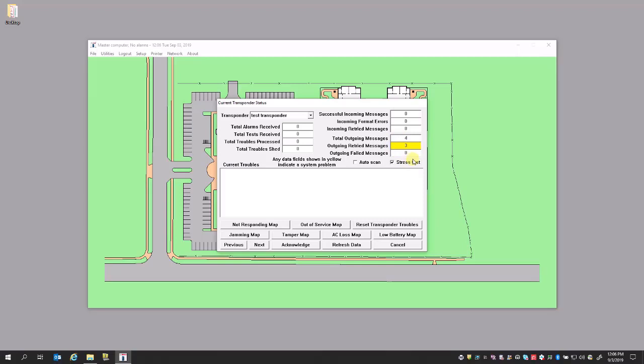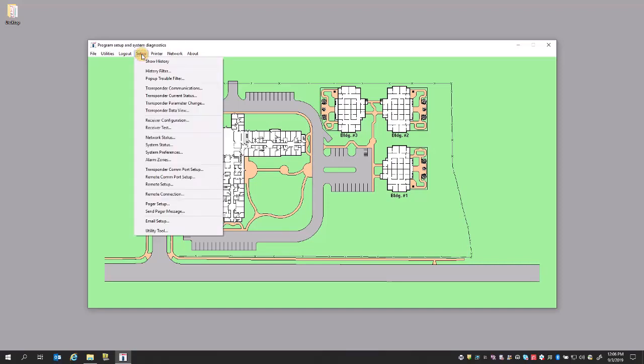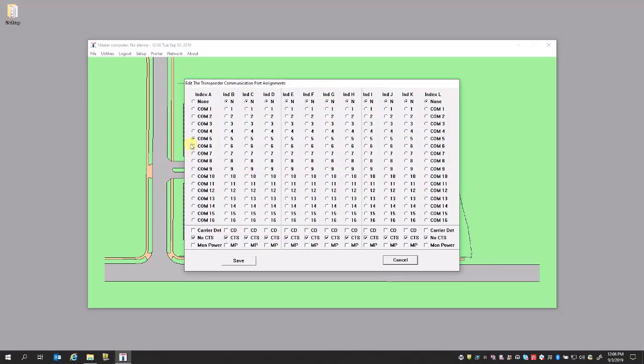We go ahead and do Reset Transponder Troubles and then we do a Stress Test. Right here you can see that our stress test is failing because we have information going out but nothing coming back. We're going to uncheck Stress Test and hit cancel. Now we're going to check our Comport Index to make sure that is set up correctly. We do that by selecting Setup, Transponder Comport, and we see that we have Comport 5.